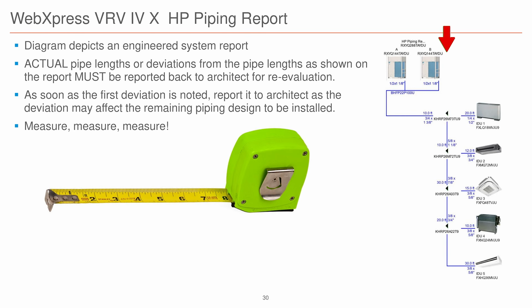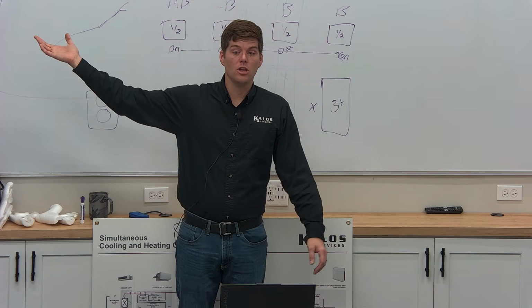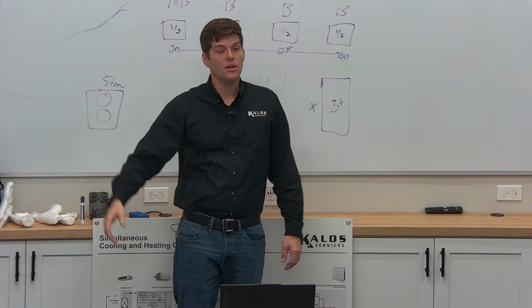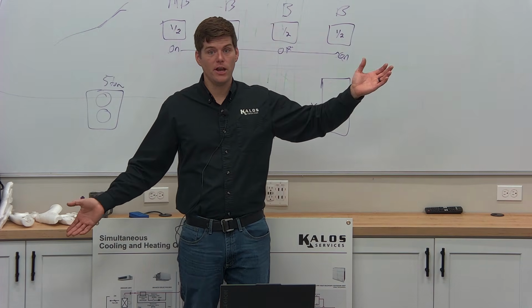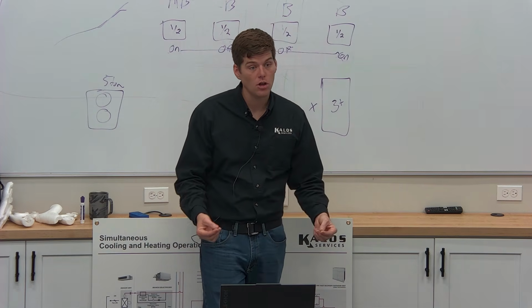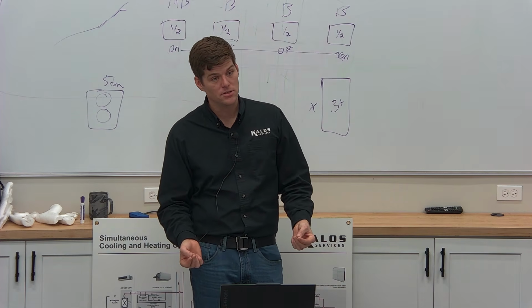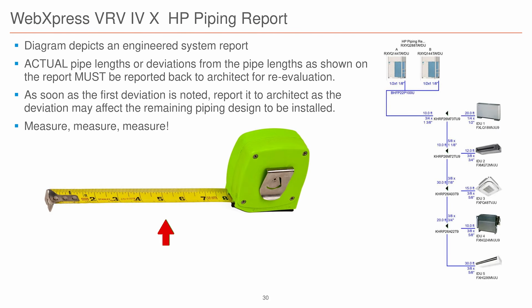Then you'll see here VRV Web Express on the right-hand side of the screen. This is the report that's generated, right? So I go out and I say, hey, based upon the drawings, this is what it should look like. You go and install it. And it's 10 feet different in a bunch of different areas. It is your job as the installer to document those changes, or not even document the changes, just measure your lines. Go off this report, cross it out, 10 feet here instead, 4 feet here instead, 5 feet here instead.